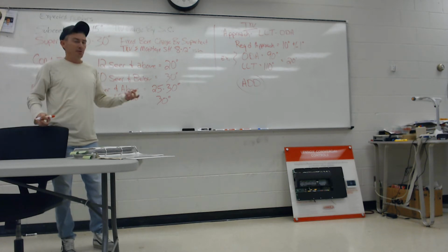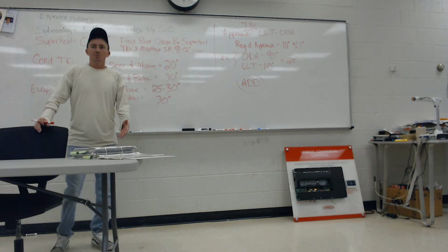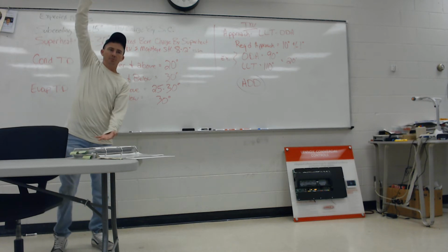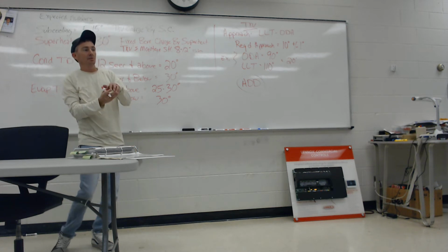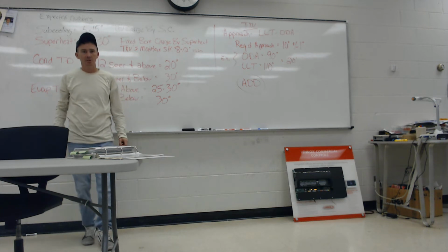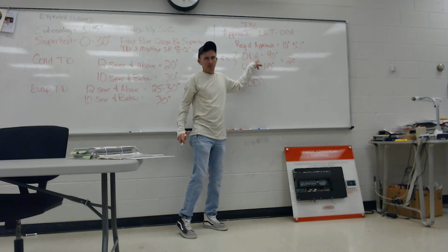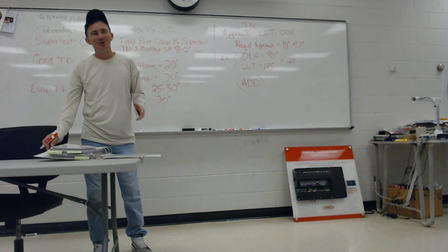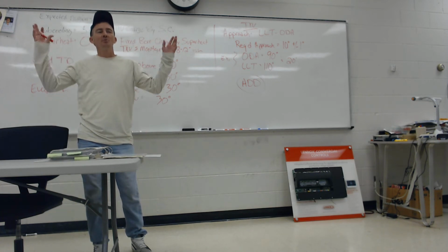But anyways, long story short, yes, add refrigerant to drop your approach, recover refrigerant to make that approach wider. Because if you pull gas out, now the TXV is going to start opening, it's going to go through the condenser faster, it's not going to reject as much heat. The longer it stays in the condenser, the closer we can get it to this outdoor air temperature. Good stuff. I love asking that question in class. It's almost always a 50-50 split. And then once you see it, it's like, boom, got it.